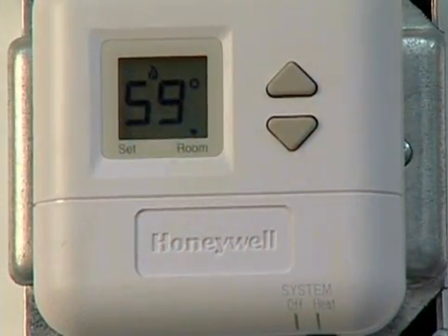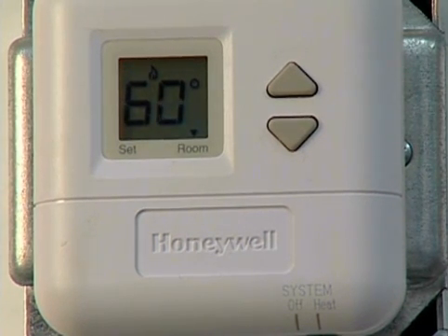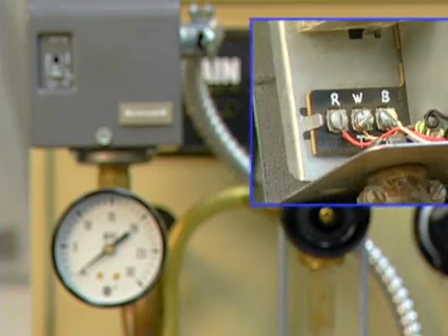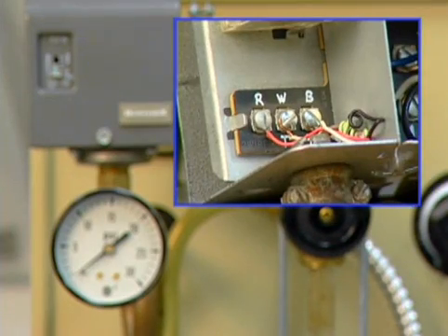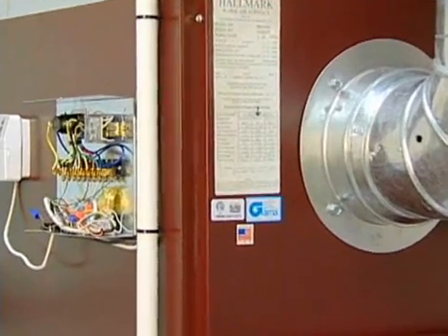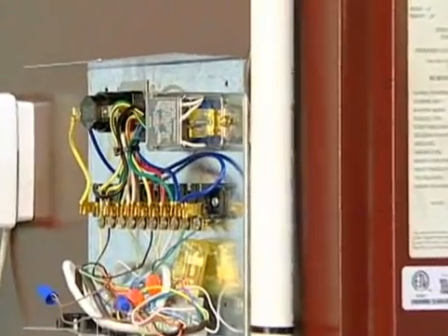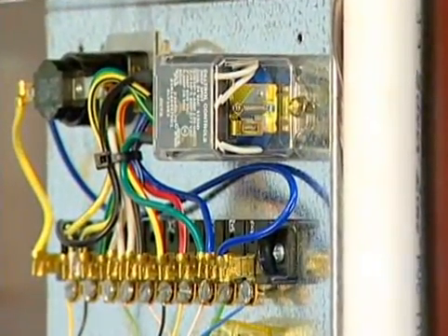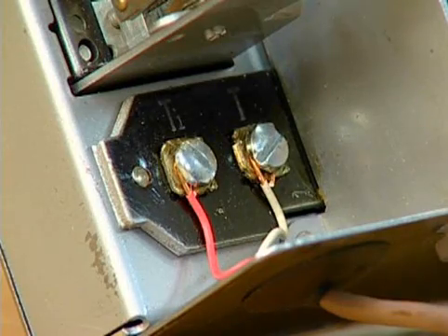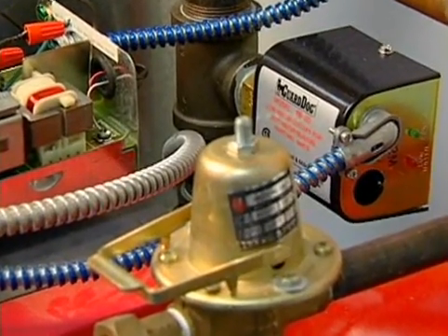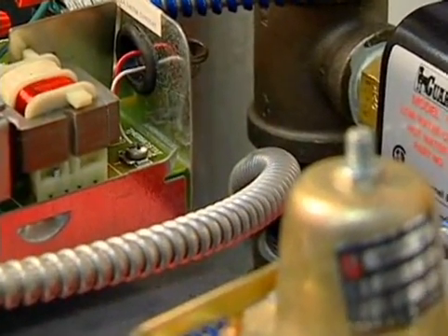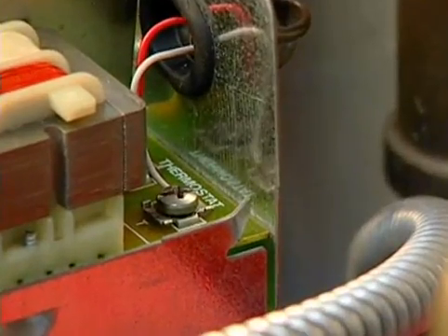The low-voltage circuit is closed when the thermostat senses the need for an increase in room temperature. When the thermostat is satisfied, it opens the circuit. In steam boiler applications, the thermostat is connected directly to the primary control. In warm air applications, the thermostat may be connected to a separate furnace control board or directly to the primary control. In hydronic or hot water systems, the thermostat is commonly connected to an aquastat or a switching relay.